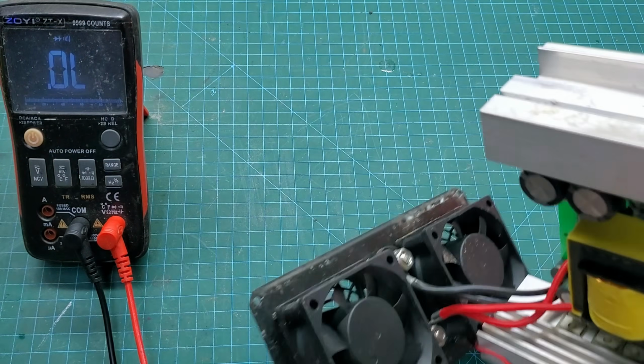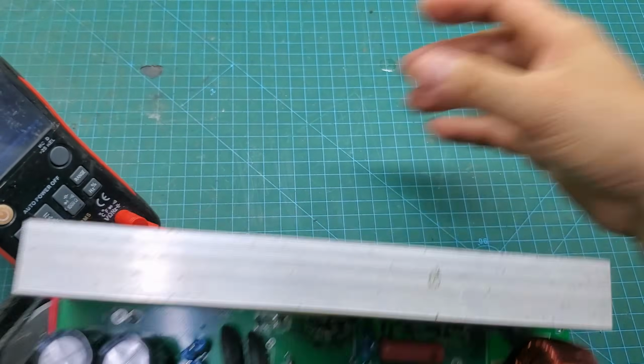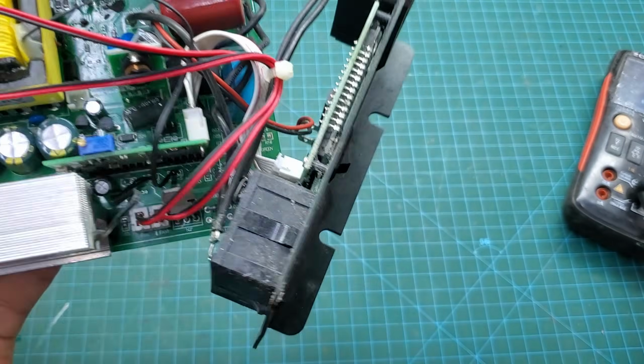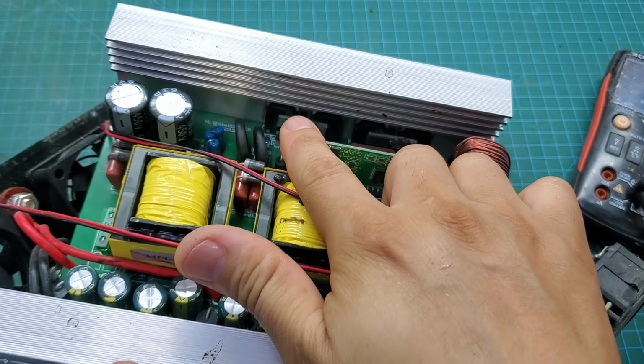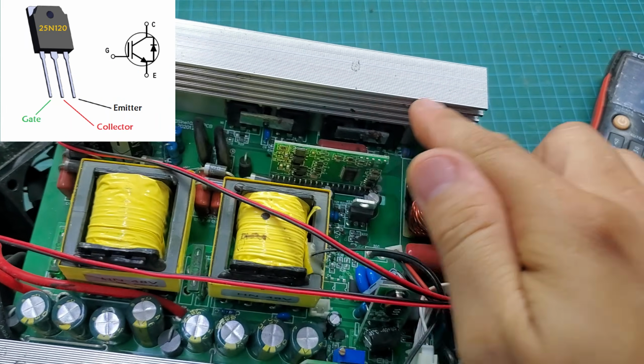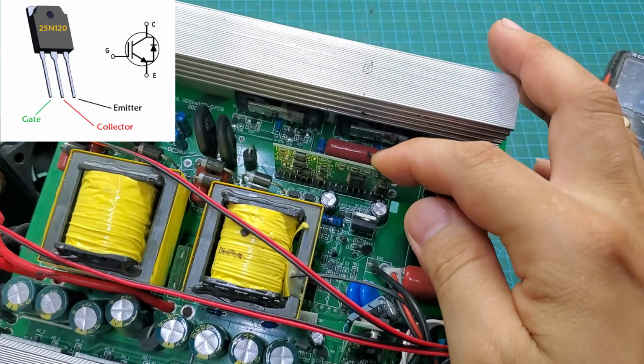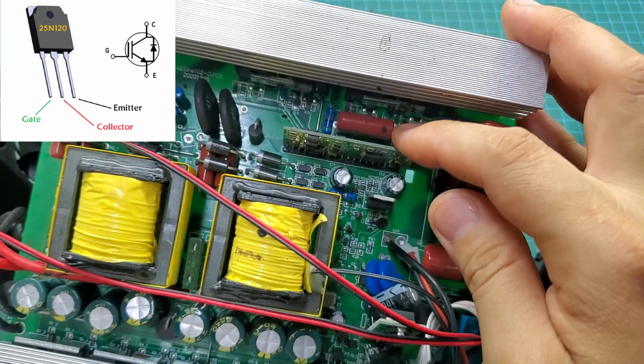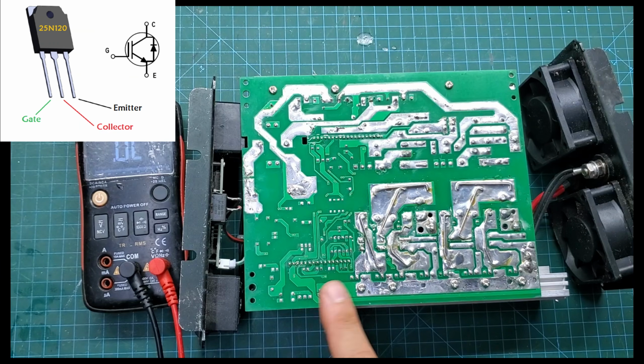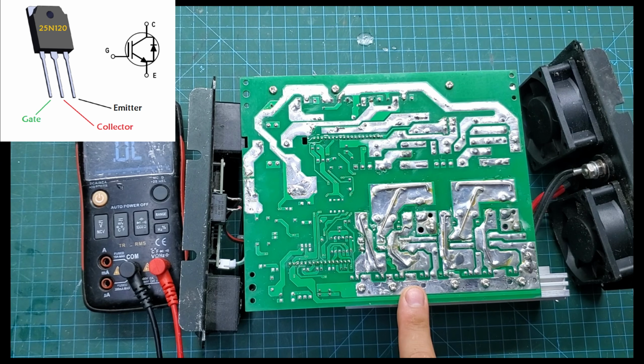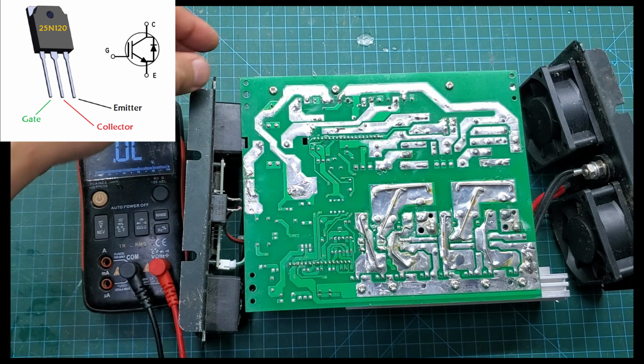Luckily, all the MOSFETs are still in good condition. Next, check the 4 IGBTs in the DC-AC stage. The method is similar. Place the black probe on the collector, C, and the red probe on the emitter, E. If the reading is around 0.3 volts to 0.45 volts, the IGBT is good.